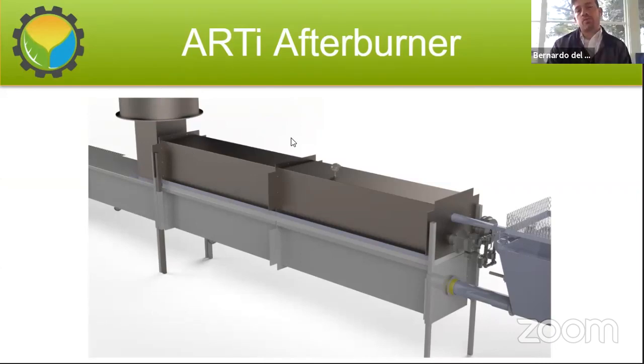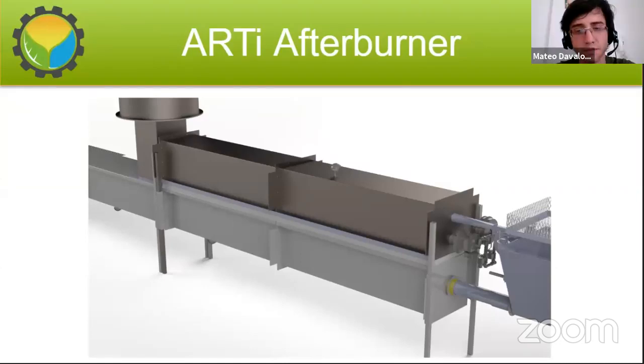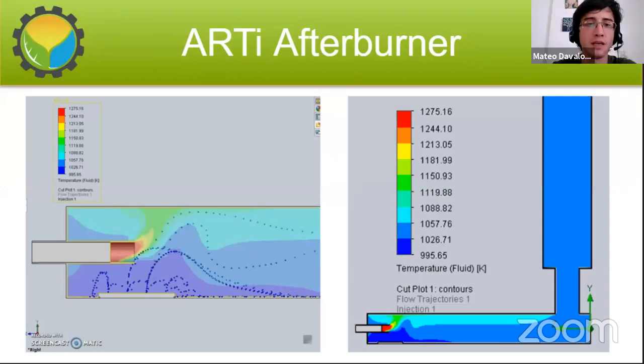And for regulations, so people understand: VOCs are volatile organic compounds, basically smoke. When you start the equipment with a tricky material, you might not get the right temperatures with a small amount of energy, or when you turn off the machine, VOCs and smoke can be produced. In those scenarios, regulators ask us to install an afterburner, since without it that smoke would come out. In that black box on top, we assist combustion with propane to reach temperatures of around 800 to 850 degrees Celsius, with a residence time of about 1 second for those gases. When you do that, all the organics break down into CO2 and water—that is the afterburner's purpose.